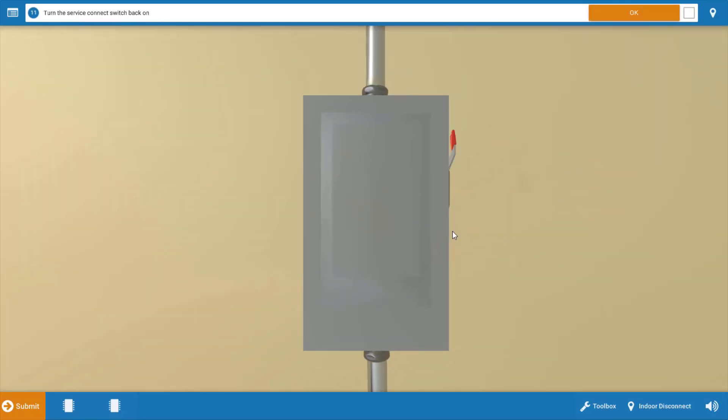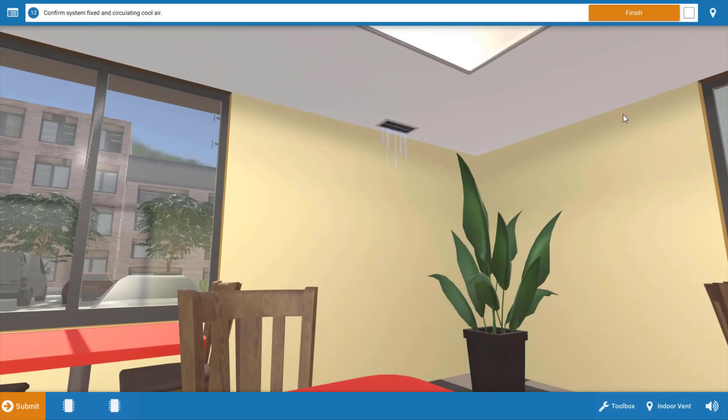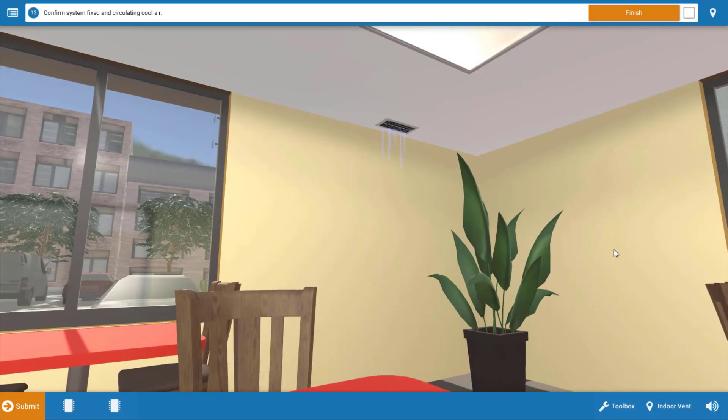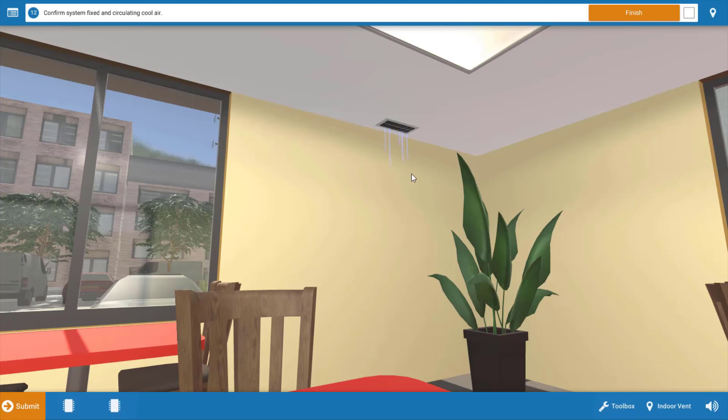After turning the power back on, I recommend you watch one full cycle of operation to make sure all the loads are functioning properly. You may want to pull the filter and check it for cleanliness. Replace it as necessary. This gives the customer a little added value on the service call. Now we can go up to the space and verify that cold air is being received through this ceiling diffuser. And we can see from the graphic here that in fact it is.